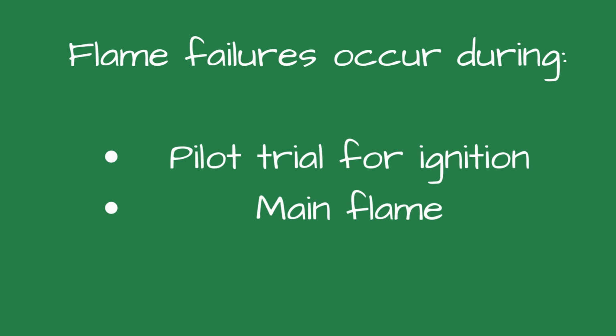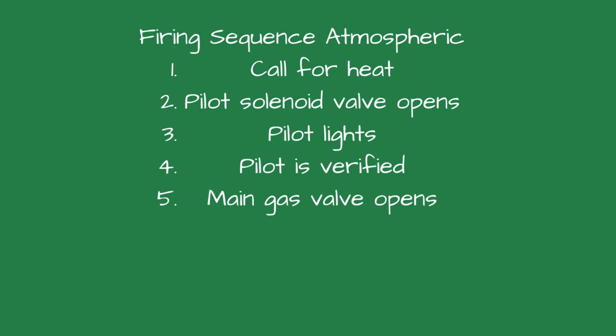To get started, let's understand the firing sequence. Before grabbing tools, mentally walk through the burner sequence. Here's how it works for two common boiler types. On an atmospheric burner, you get a call for heat from the thermostat. The pilot solenoid valve opens. The ignition transformer sends high voltage to the electrode. The pilot flame ignites. The flame safeguard verifies the pilot, usually within 10 seconds, and the main gas valve opens. The pilot lights the main burner.